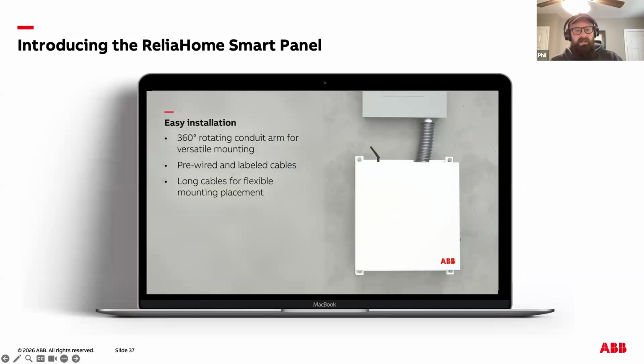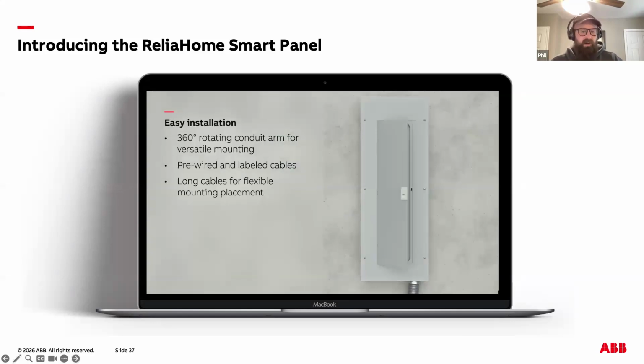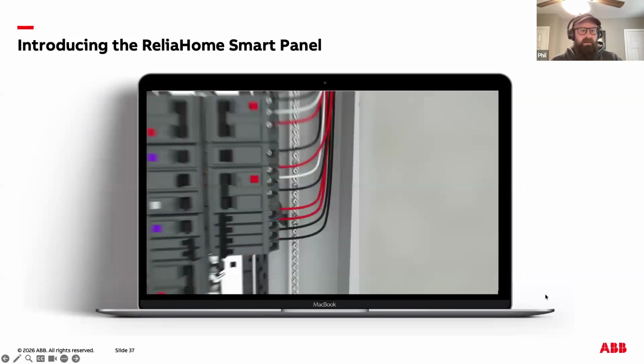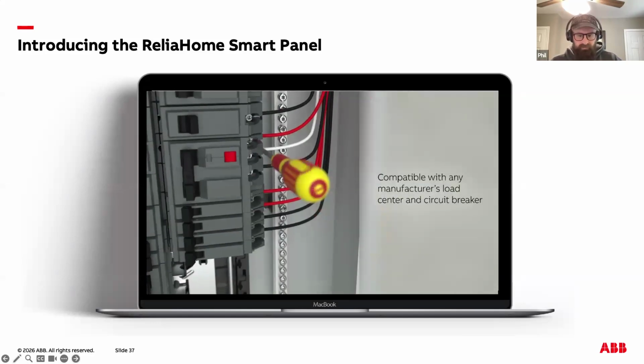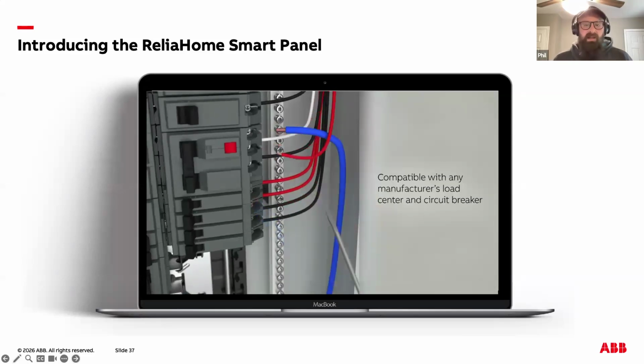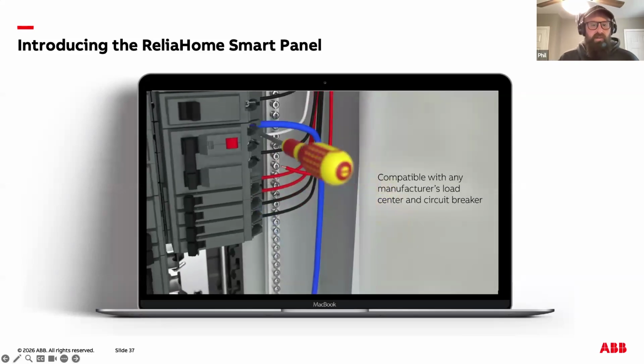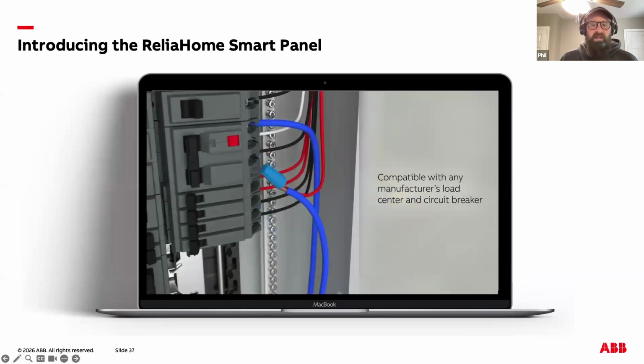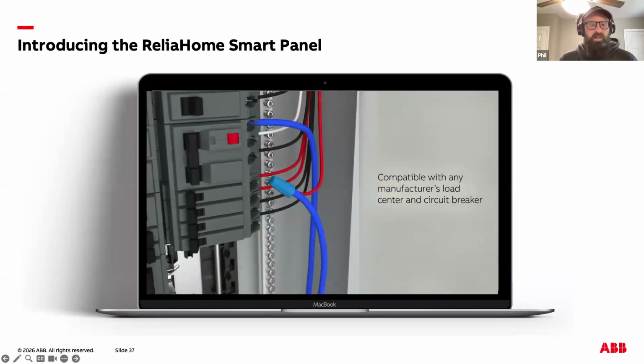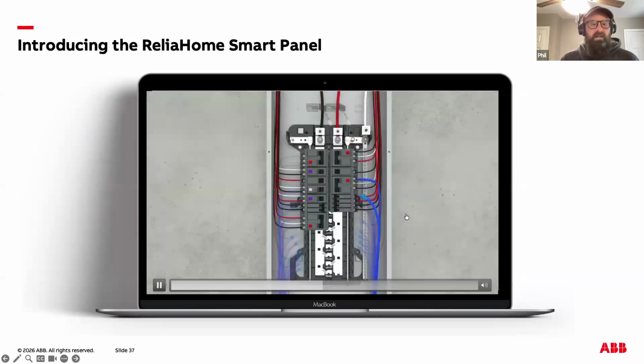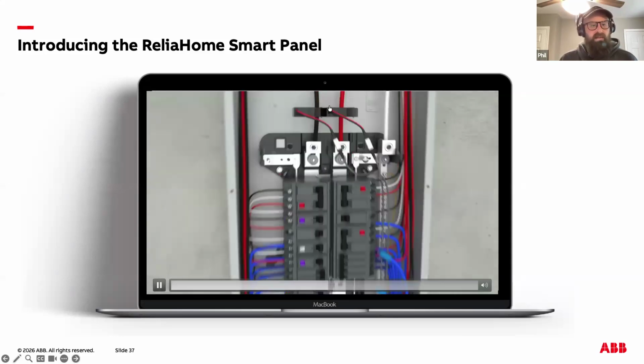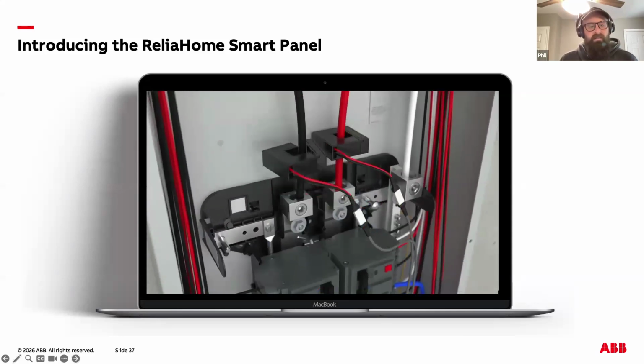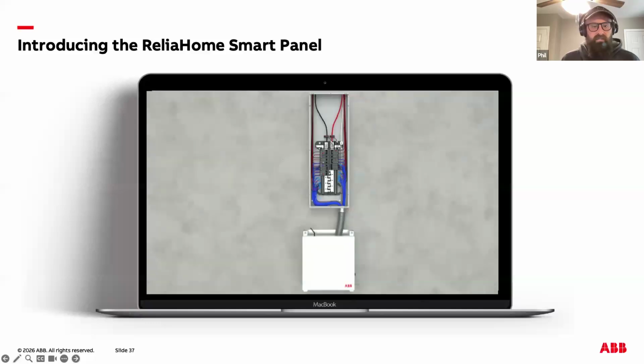The smart panel intercepts the circuit between the existing breaker and the existing home run, as you'll see on the screen, making it easy to install. Each unit comes pre-wired with a set of main CTs and grid outage detection built in. And you see the main CTs go on the service conductors or feeders, and that's pretty much the whole installation.